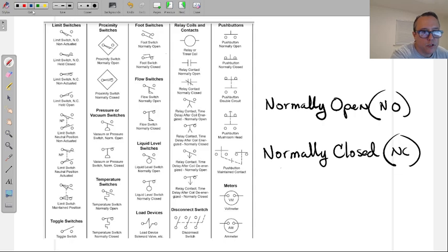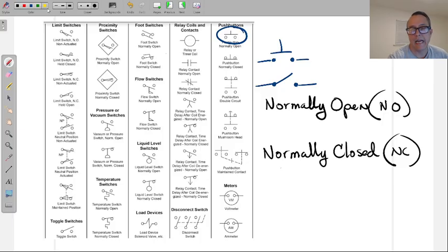If you are an open switch, it doesn't matter which one, limit switch, proximity, flow, foot, liquid, doesn't matter which one we say. If you are an open switch, voltage is not going across you right now. Same thing for our push button, it just has a different symbol, a little top hat. If you are in the normally open position, voltage has not gone across to the other side of the switch yet. If you are in the normally closed position, then yes, because it's closed.